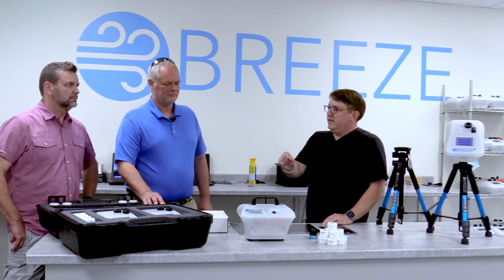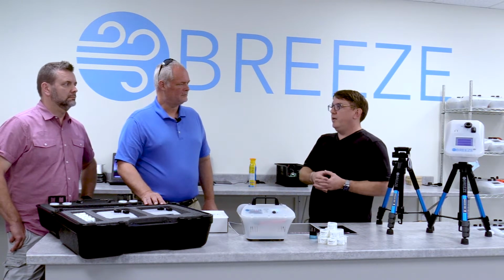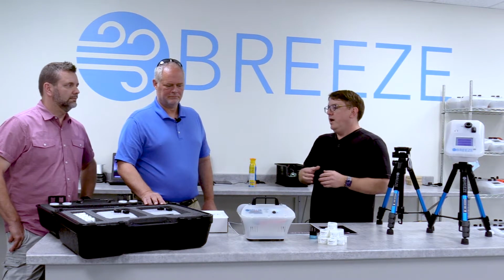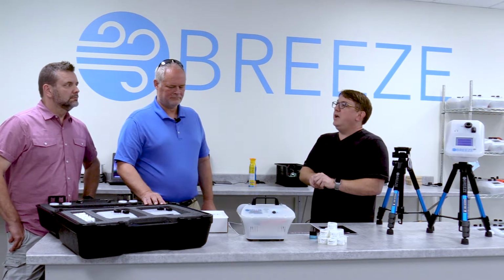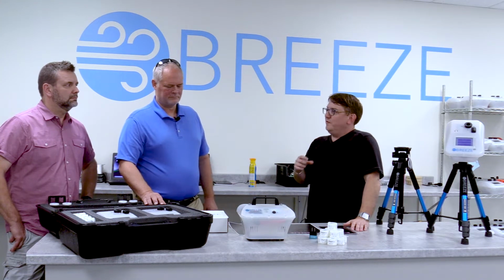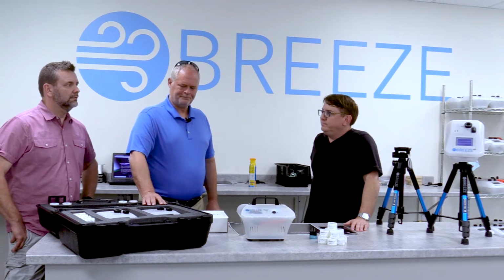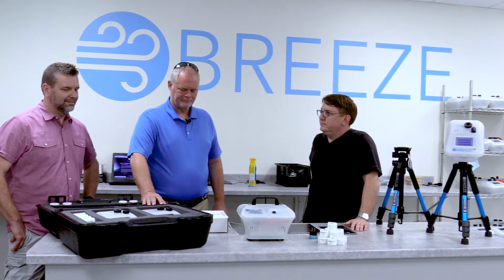The mold testing devices, the vacuum pump, those ones you do not, because they have an onboard calibration device and a simple one. If you want to send it back to us, you can. We can also send you a unit that will confirm that it's pulling the 15 liters per minute. I actually have that one.